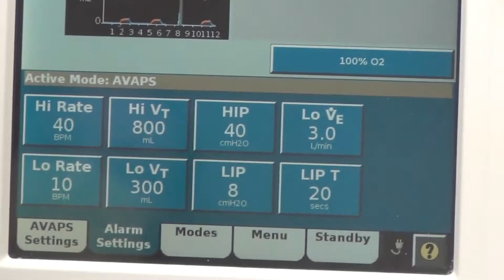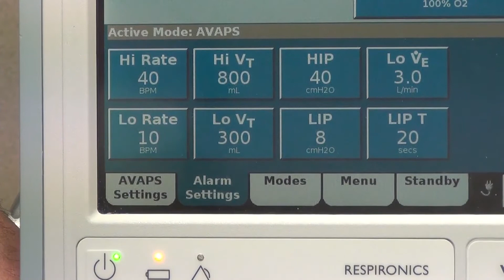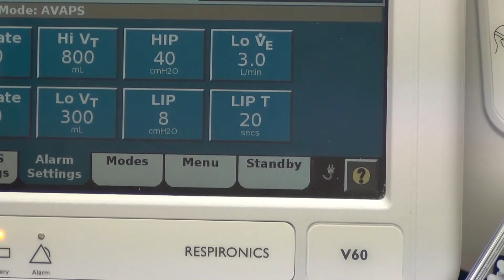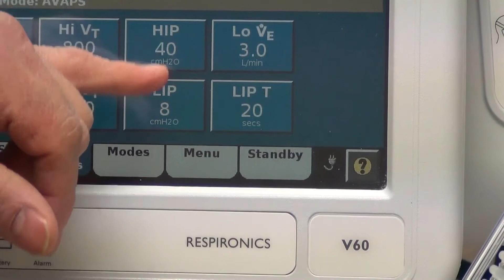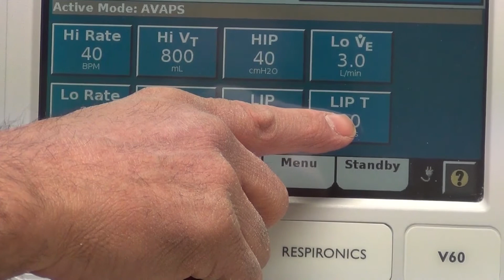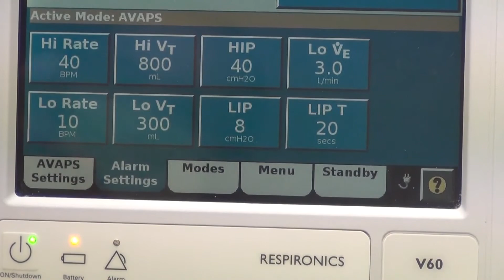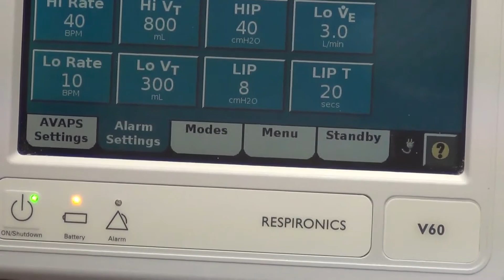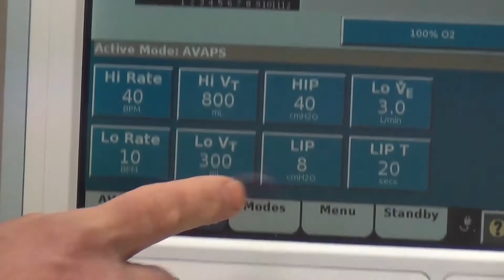Low pressure alarm is, again, if we were to disconnect, we get a low pressure. We want that to be above our PEEP. If you go back to our settings here, our PEEP is set at 5, so I'm going to go back to alarms. We want this at least above the 5. That way we know if there's a problem, a disconnect. And this right here is a low pressure time delay. So for instance, if the pressure were to drop and go below 8, it takes 20 seconds for that to activate the alarm. So it's giving time for, let's say you just took this off for a second and repositioned it. It just allows a little bit of time before the alarm goes fully off. But that is a low pressure alarm.